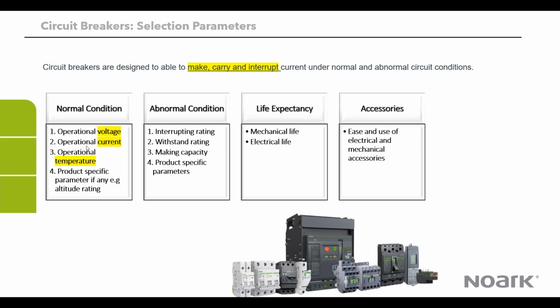The other thing to look out for is the abnormal condition. So here it's important to know what the interrupting rating is. We define the interrupting rating of a circuit breaker as the maximum short circuit current that the breaker can safely interrupt without damage to itself. So it's the amount of fault current that the breaker can safely interrupt. That is an important parameter when you're trying to select a circuit breaker. You need to make sure that you know what that value is, and typically it comes from the design.